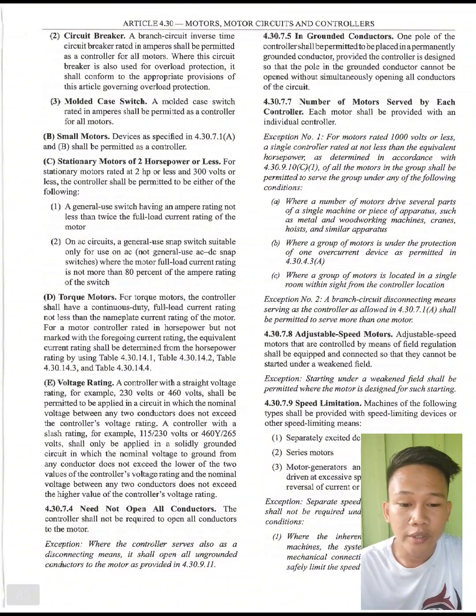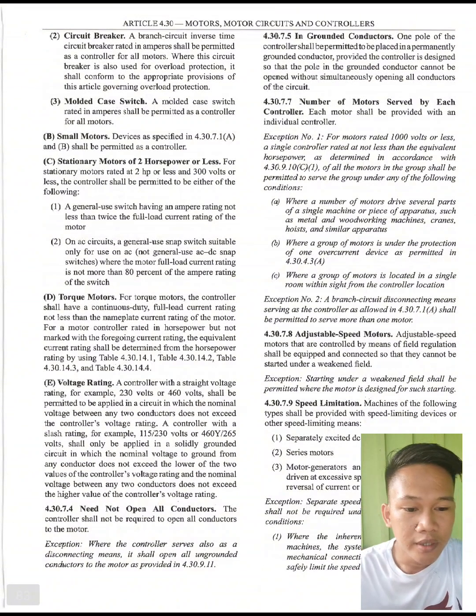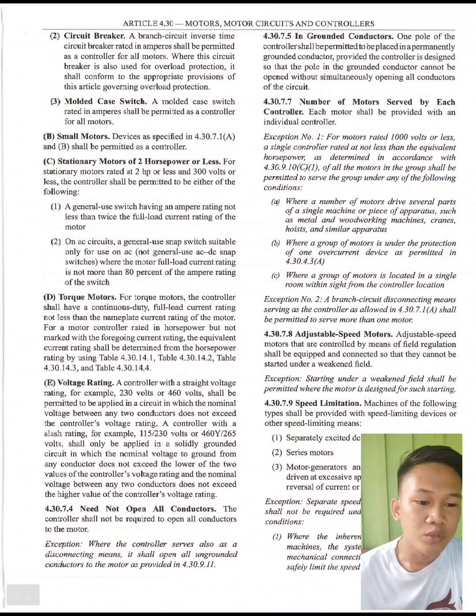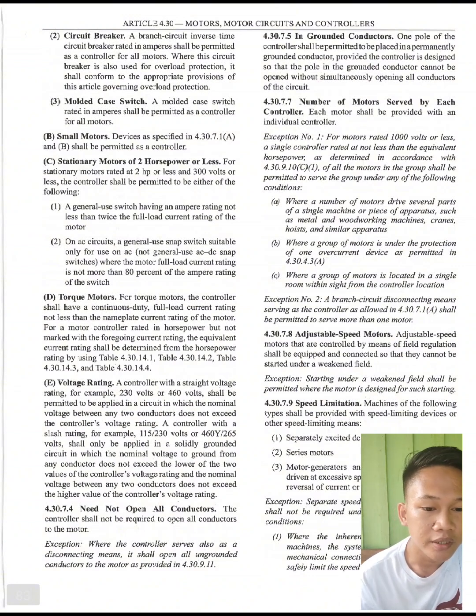Next we have 4.30.7.5. Grounded conductors. One pole of the controller shall be permitted to be placed in a permanently grounded conductor, provided the controller is designed so that the pole in the grounded conductor cannot be opened without simultaneously opening all conductors of the circuit.